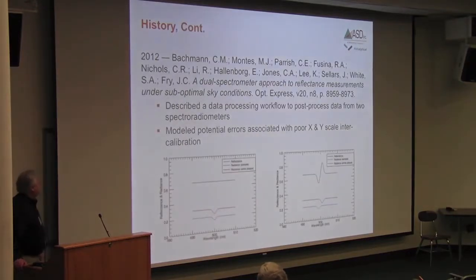There was a paper that came out in 2012 where the author developed a workflow for collecting matched spectra on two systems, one fixed looking at a white reference and the second one that could move around, and did a lot of modeling of the errors you get when you don't properly intercalibrate the X and Y scale. At the bottom are some graphs showing modeled spectra. If you have a feature like this, and everything lined up right in the wavelength scale, they ratio out very nicely. But if they're offset relative to one another, you get a feature that looks something like this. And this is, in fact, what we use to manually make the adjustment back in the early days.